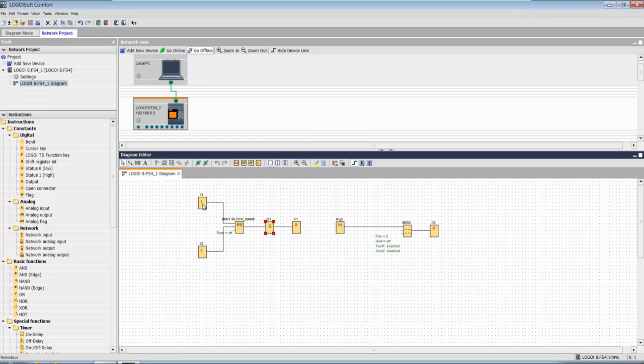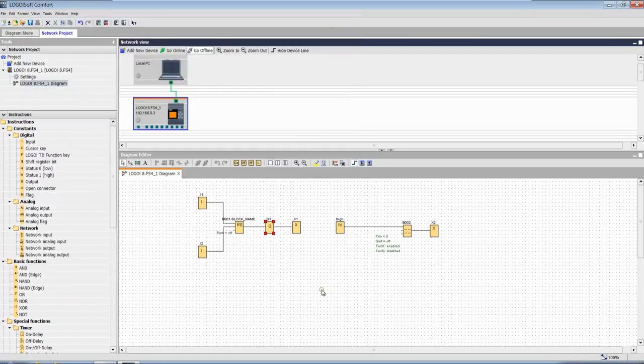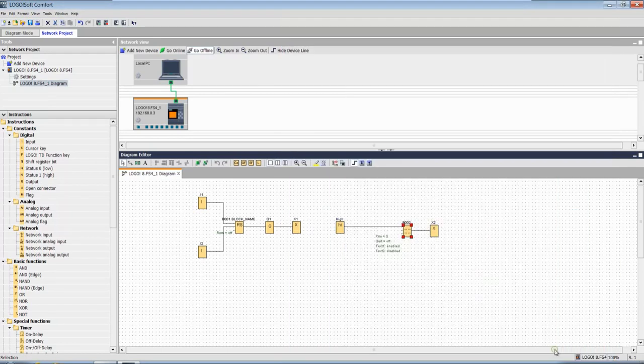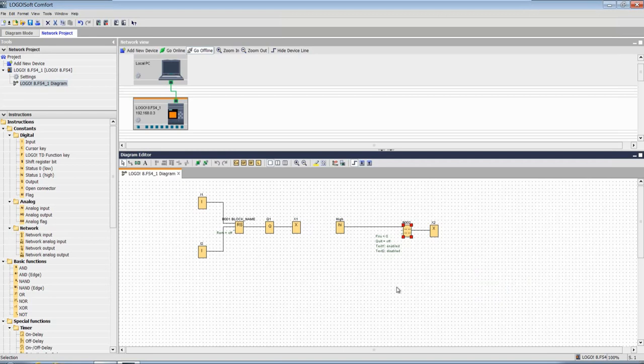But this comment is not here. Block name is there, and let us check about the tag name. So we have also lost our tag name in our uploaded backup. So these are the limitations - your comment is gone and the tag names that you have given are also not available in your uploaded backup.